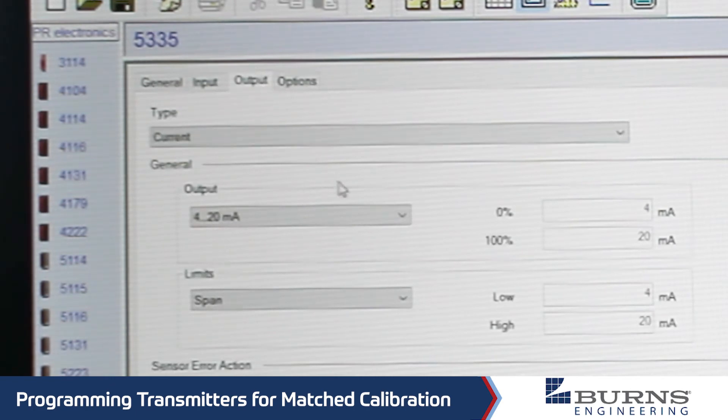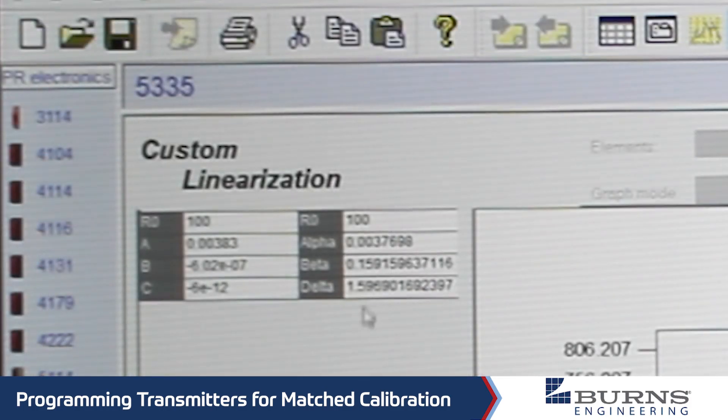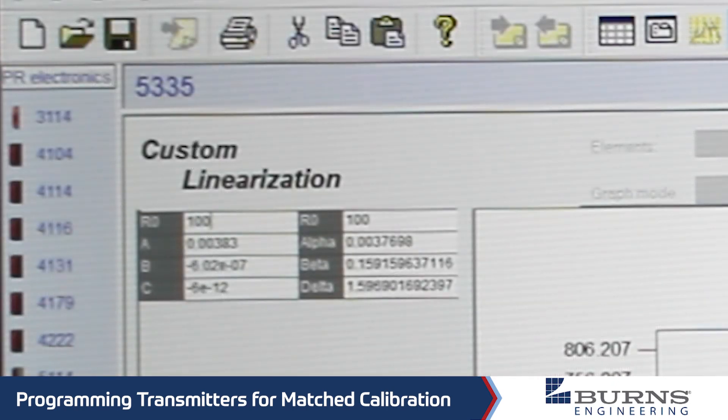Next we go to the output tab — there are some other options here you can select, and these are all fairly well documented in the instruction manual. If you have other questions, feel free to contact us. Next we go to the options tab, and here is where we enter in the calibration coefficients. We want to make sure this is selected to Callendar-Van Dusen coefficients, and we click Specify. This is the table where you will enter in all of those numbers, like the ice point resistance — for example, it was 100.0446 — so we just plug that number in along with these other coefficients.